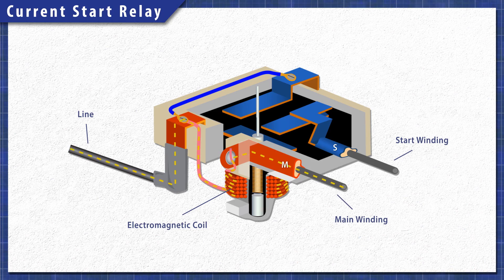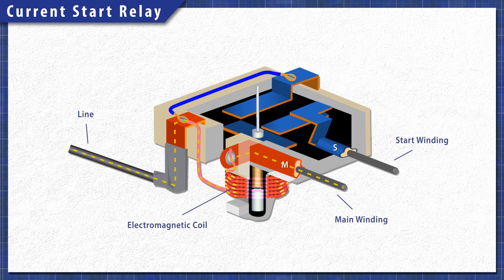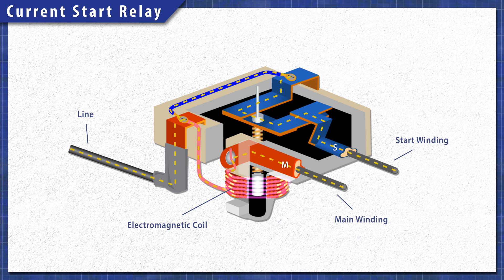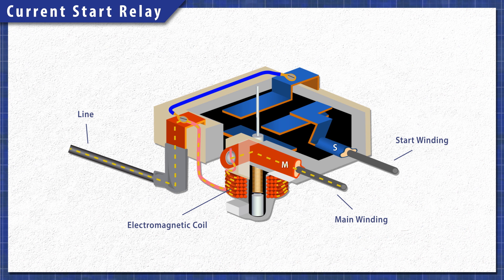A current start relay works differently. When current flows through the coil, the magnetic field pulls a plunger and closes the circuit. The current drops shortly after startup, which releases the plunger, and disconnects the start winding.